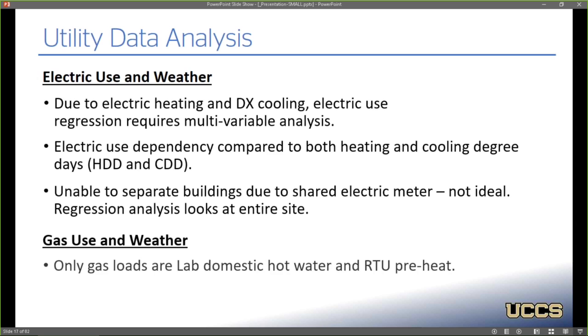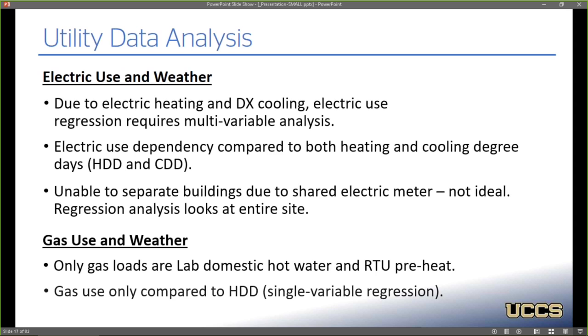Looking at the gas use, the only gas loads we have here are the lab domestic hot water, which is an extremely small load, and then the preheat of the supply air at the rooftop units. And so we really would just expect this to have a correlation with heating degree days, and so this would be a single variable regression analysis.